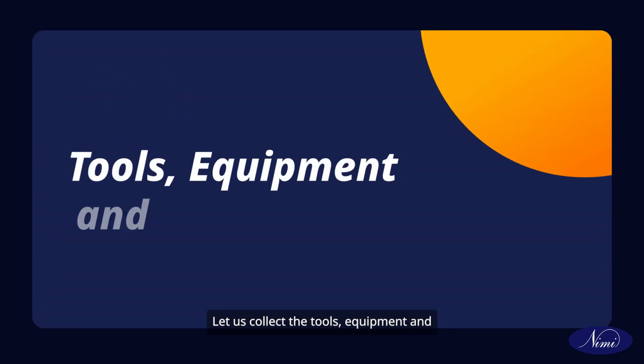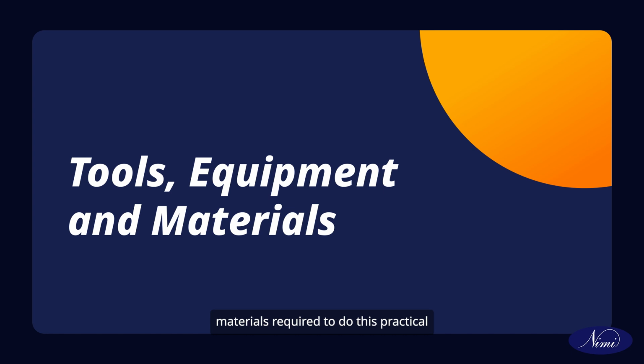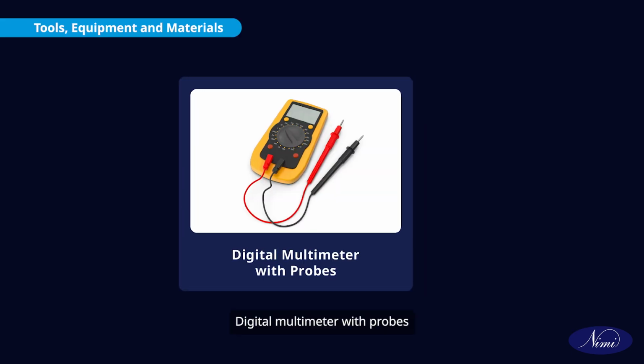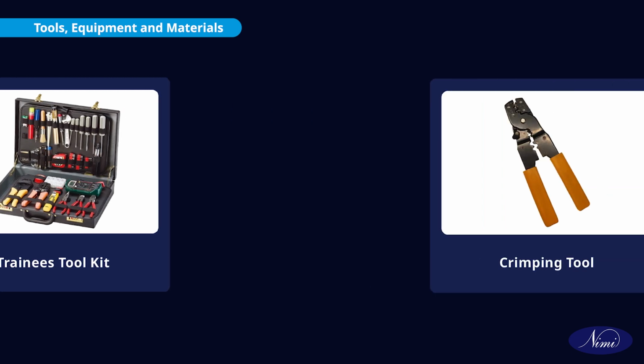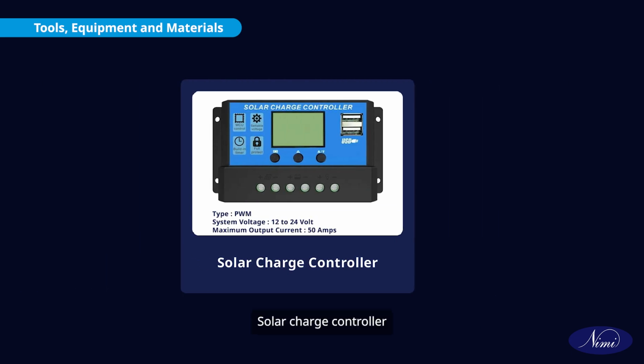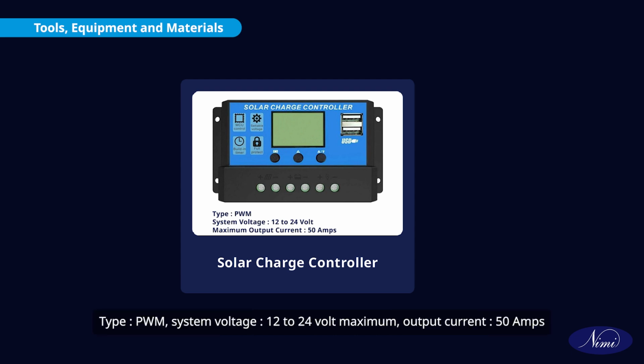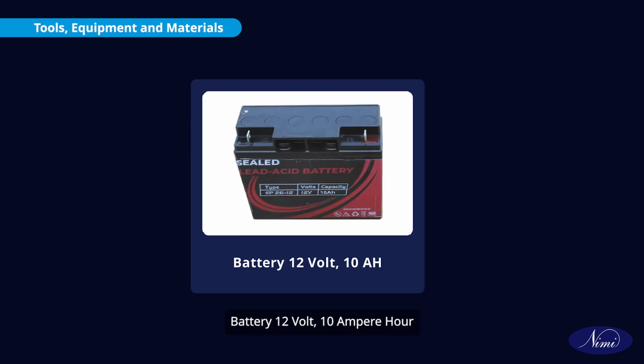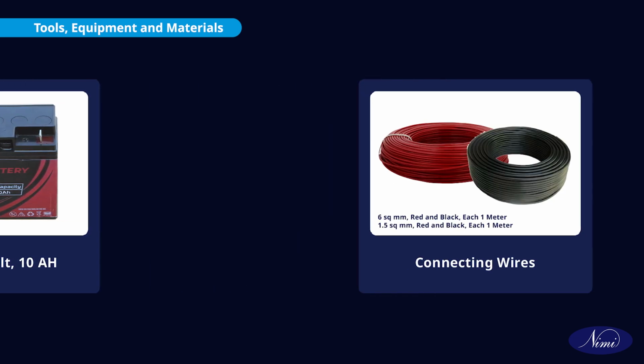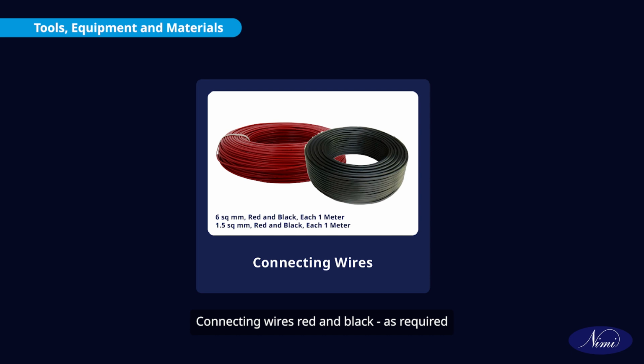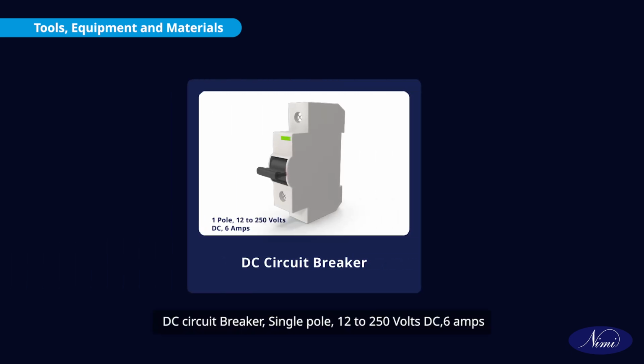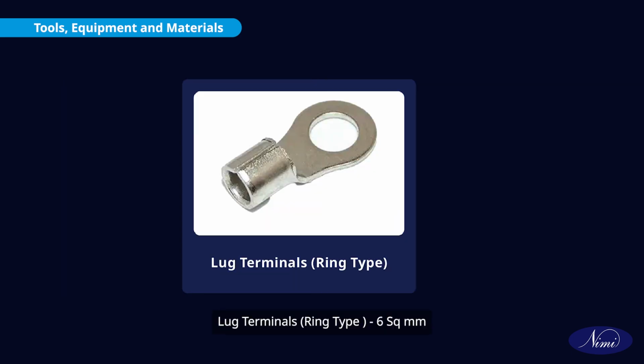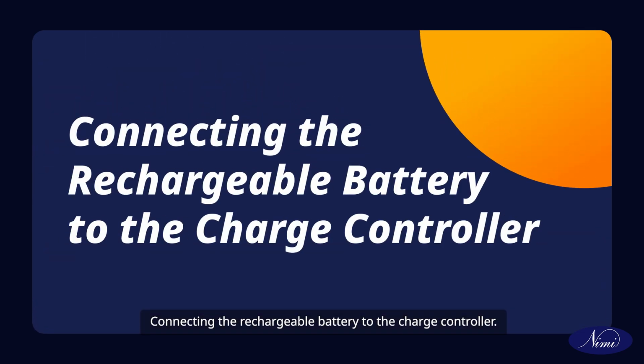Let us collect the tools, equipment and materials required to do this practical: digital multimeter with probes, trainees toolkit, crimping tool, solar charge controller type PWM with system voltage 12 to 24 volt and maximum output current 50 amps, battery 12 volt 10 ampere hour, connecting wires red and black as required, DC circuit breaker single pole 12 to 250 volts DC 6 amps, and lug terminals ring type 6 square millimeter. Now, connecting the rechargeable battery to the charge controller.